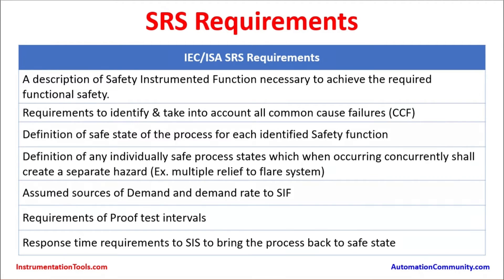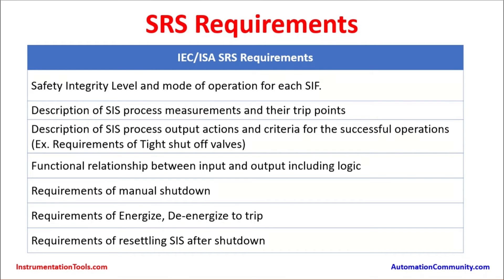Further SRS requirements include: proof test interval requirements; response time requirements for the SIS to bring the process back to a safe state after an incident; safety integrity level (SIL 1, SIL 2, SIL 3) and mode of operation for each SIF — typically low demand mode; description of SIS process measurements and their trip points; description of SIS output actions and criteria for successful operation; and the functional relationship between sensor inputs and final element outputs in the safety logic.